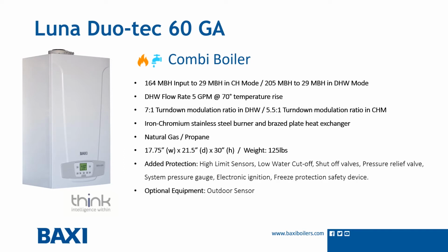Our GA60 is our biggest combi unit. It has a BTU rating of 164,000 to 29,000 in central heating mode and 205,000 to 29,000 in domestic hot water mode, which means the GA60 can produce 5 gallons per minute at a 70-degree rise in temperature. The GA60 can handle up to 3-bath home with normal flow fixtures. The GA60 is 17 inches wide by 21 inches deep by 30 inches high and weighs 125 pounds. Unlike the smaller combi units, the GA60 does not come with a built-in expansion tank.